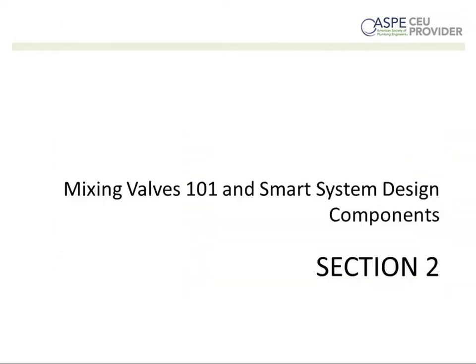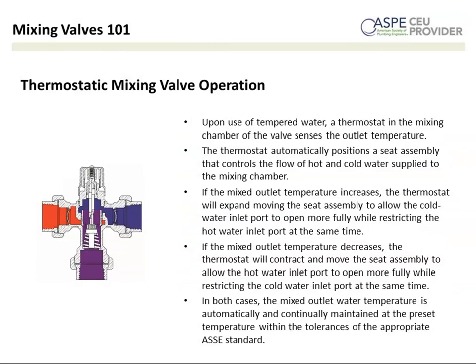I'm going to skip that slide. So we're going to go right to a little bit more specifically about standard mixing valves, and then talk more about digital, a little bit more specific. So basically, thermostatic valve operation. There's a lot of text on this slide. I'm sure a lot of you are familiar. You're bringing cold water in one side, hot water in the other, and you're mixing it. And at the outlet, you're providing a safe mixed hot water temperature.